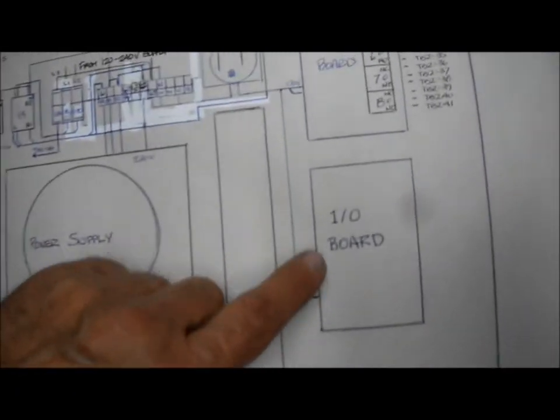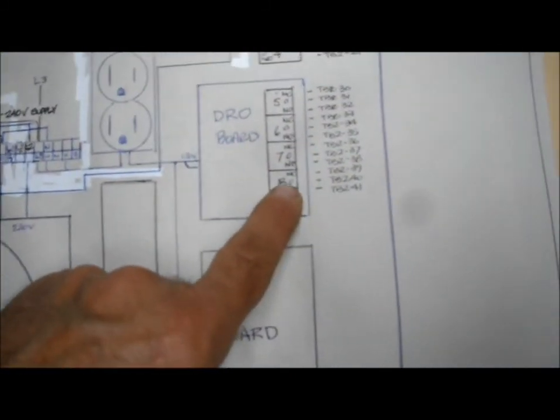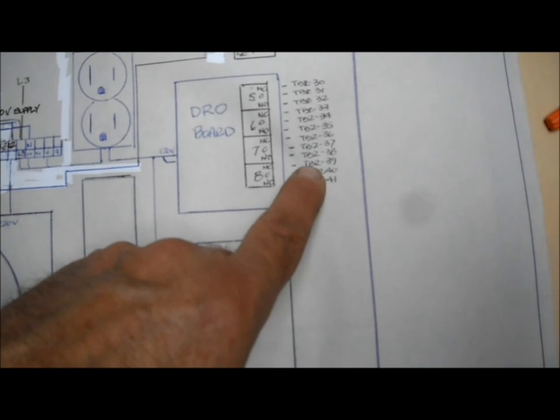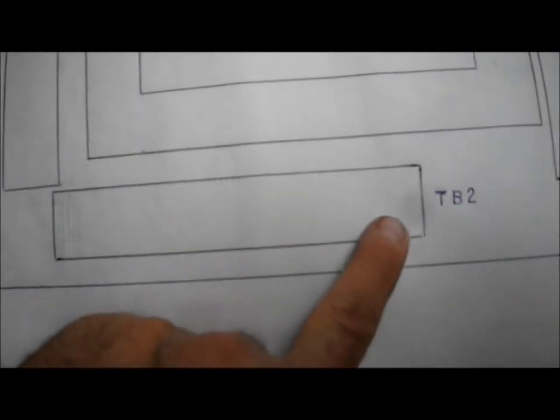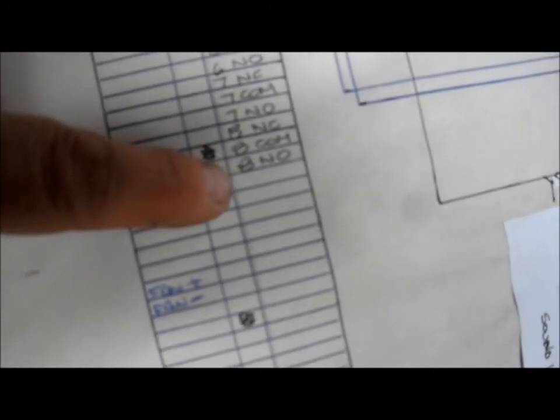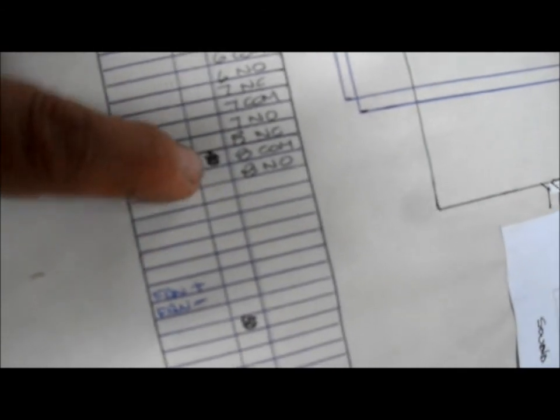And one more sheet, I think, basic layout. Those are all the relays that I had showing the terminal connectors. So we know on relay number eight, for instance, the normally open contact goes to terminal block 239, and that would be TB2. TB2 is down here and it would be drawn in on the other drawing. Actually, if you went over here, TB2 39, and it will show you, there you go, NO and or normally closed, there's 40, there's 39.